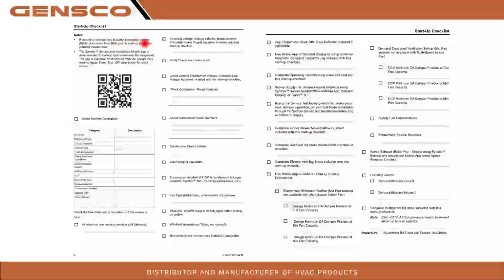Does the unit have BAS? It's going to want to know. Did you verify the crankcase heater is on? What's your fan type? Is there an economizer installed? What's your gas piping, condensate drain installed? What's your compressor serial numbers? Some of it might be overkill, but it's going to be important to have that information at a later date if you need it. It's going to save a lot of time, right?